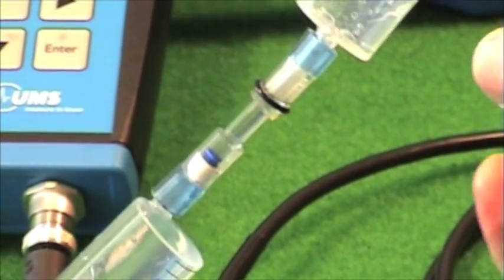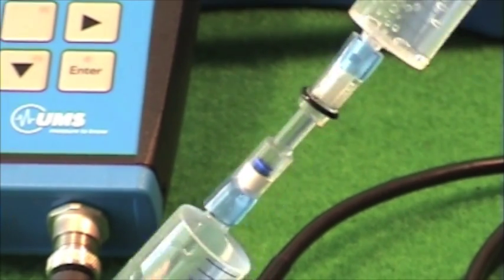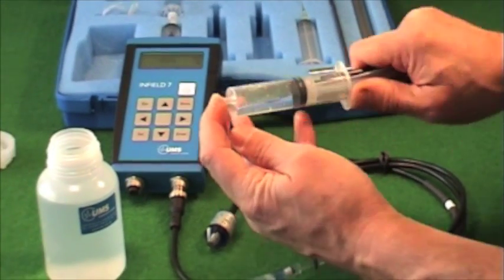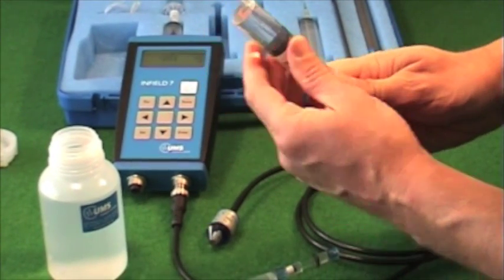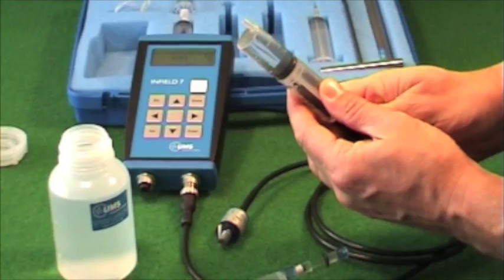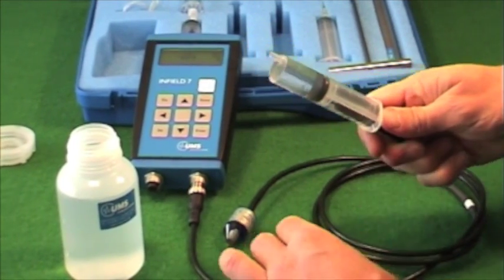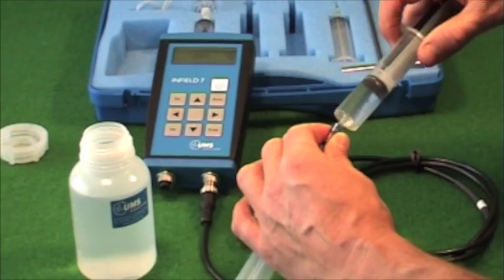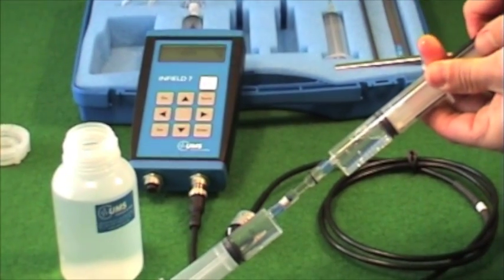Turn the syringe to collect all bubbles but don't tap on the syringe. Remove the syringe from its pipe and remove all air bubbles. Connect it again to the pipe and pull up the syringe until the black pins snap in.